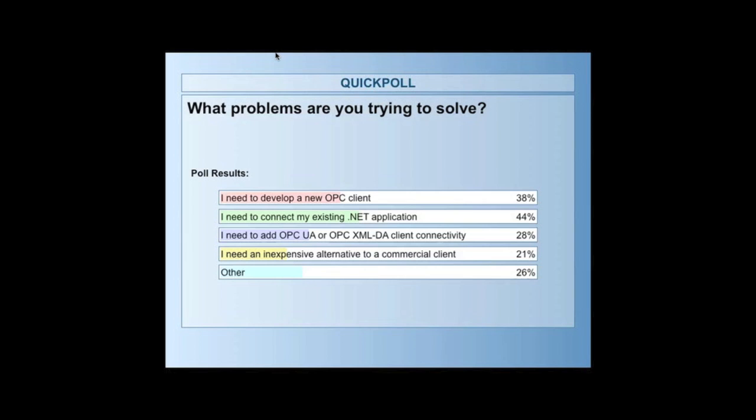One more comment. In an existing application, have an OPC client other than Kepware. Concern that it might be affecting KEPServer stability. I think Kepware server client is better. All right. Makes sense. Use the same software for connection, right? We do sometimes see that even though someone says they're following the OPC spec, they may not be following that to the fullest extent, and that oftentimes does cause communication issues. So just use software that you know is reliable, that does the work well, and it gets connected well. Thanks, Mike. Okay, I'm going to go ahead and close this poll out.